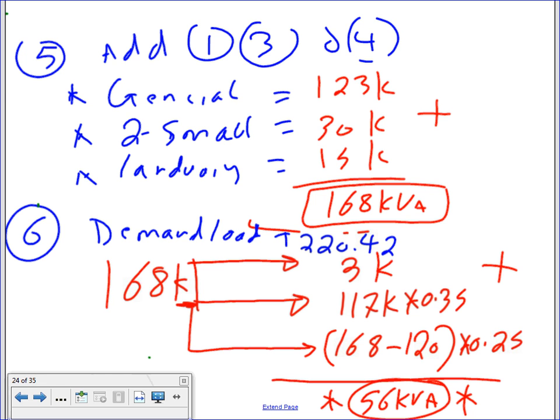Anybody know where the 117 is coming from, guys? If it's confusing you, it's coming from 120 minus 3. That's where the 117 came from, 120 minus 3. That's how you apply this table. The first 3 leave alone. The first 117, because the 3 added to them is 120, cut it by 0.35. Anything higher than 120, which is whatever you came up with minus 120, cut it by 0.25, add them up. That's it. That's a demand.